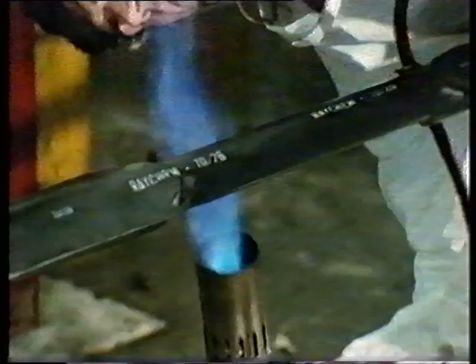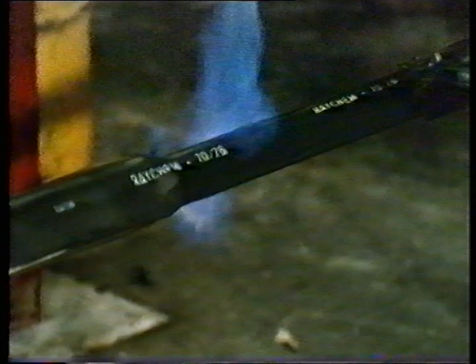Yet another seal is applied to the lead, and then it's time to restore the PVC sheath. To ensure a satisfactory bond and to act as further moisture barrier, a layer of hot melt adhesive tape is applied on and beyond the reinstated lead sleeve. The PVC sheath is in the form of a heat shrink tube, which had been run onto the cable before the joint was started. When heat is applied to it, the tube shrinks down and beds itself onto the cable.